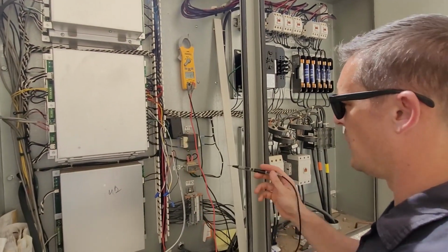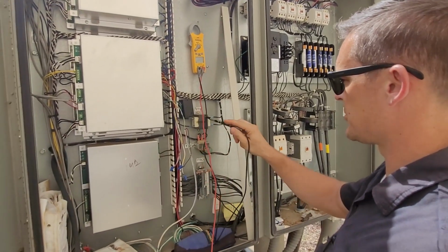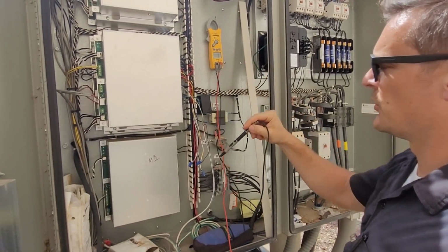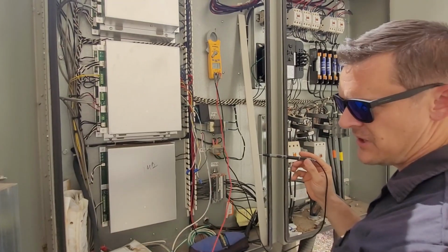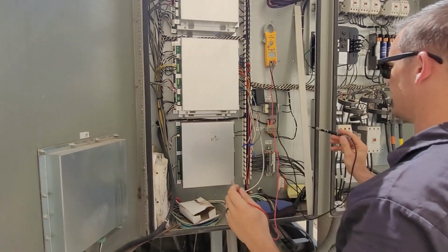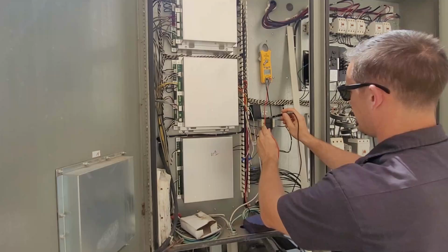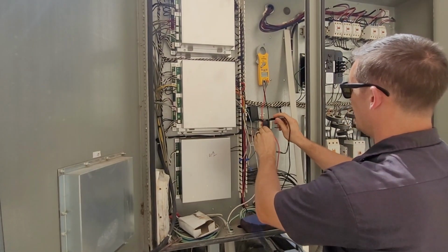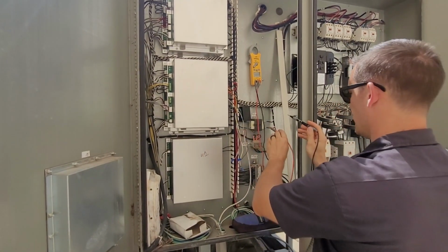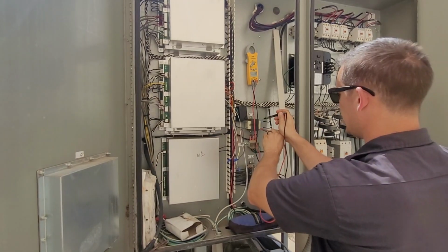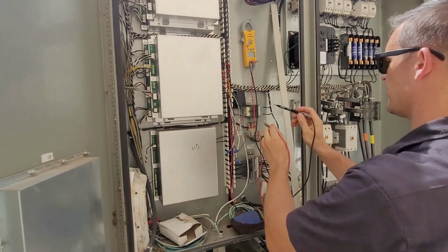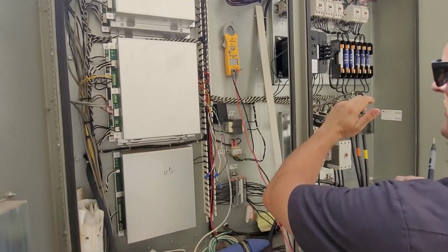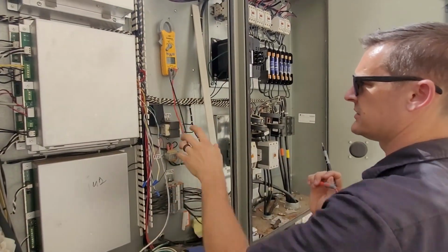But still, I wanted to check these transformers. These are typically control transformers. They probably feed these boards. Maybe they feed this. Not sure. So the next thing I do is I check the low side of a control transformer. It's 0. Let's check to see if there's anything coming in on the high side. Also 0. So my problem is upstream of all of this.